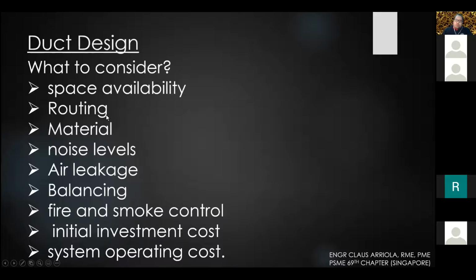So you need to route your duct away from any fire compartmented space. Then another is material, especially for smoke management. You will use a thick gauge. So usually I use 16 or 18 gauge of duct. This is very thick, a minimum of 1.2 mm thickness of duct.